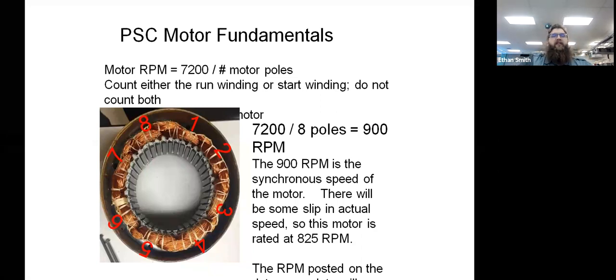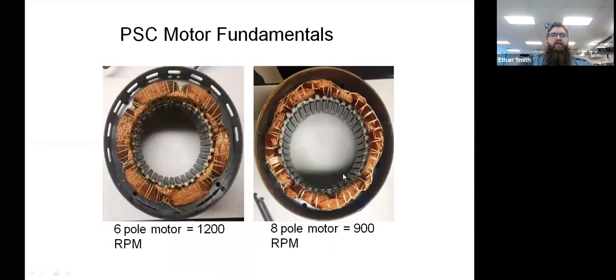Kind of a cool little thing here. So if we had 4 poles on that motor, it would run at 1,800 RPM, excuse me. Okay, so there's some other examples there. We've got that 6-pole motor that we looked at. That's a 1,200 RPM motor. The 8-pole, 900.